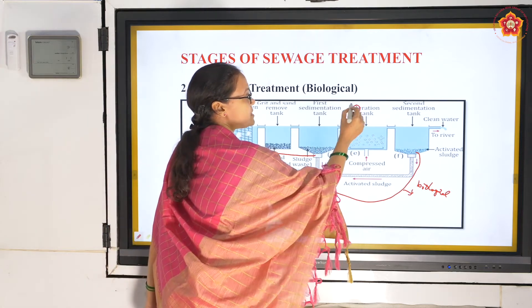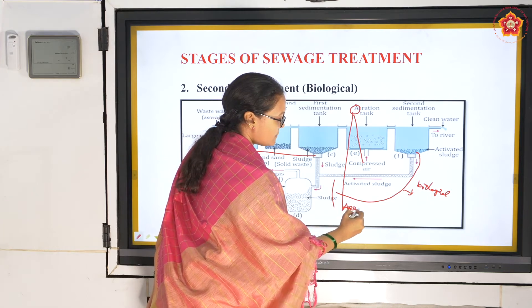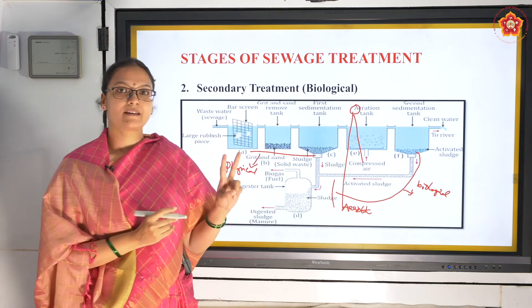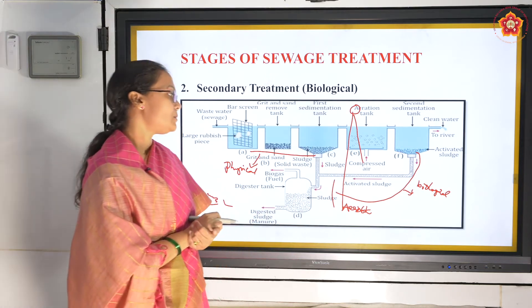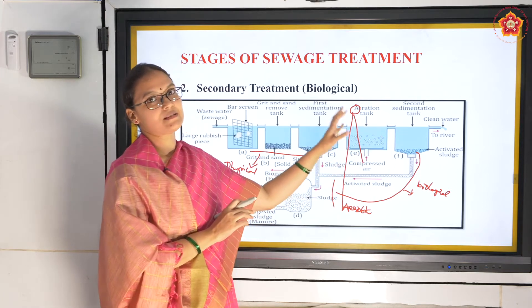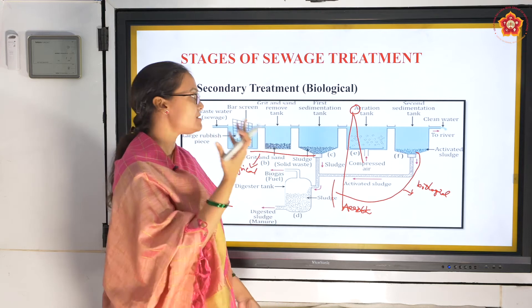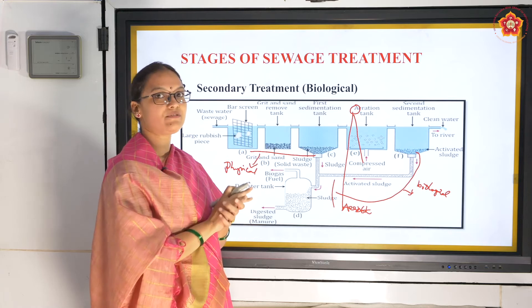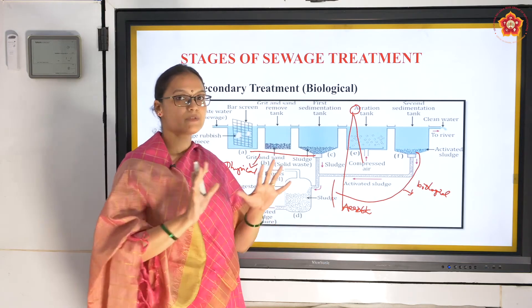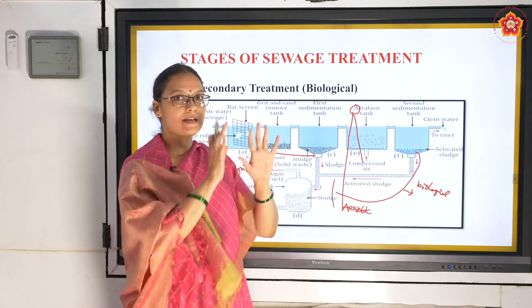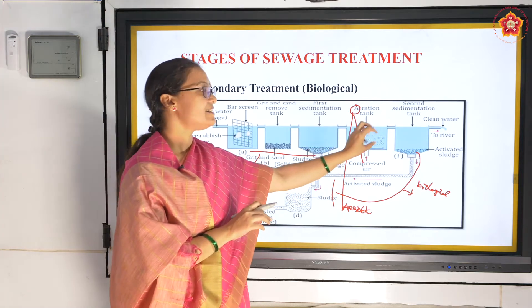In the aeration tank, two things are added: air and aerobic bacteria. The aerobic bacteria try to eat up all the organic matter present in the effluent. First aerobic bacteria are added, then air, and the tank is constantly agitated. As the aeration tank is agitated it forms something called flocs - colonies of aerobic bacteria with a mesh-like structure. The whole aeration tank is filled with these mesh-like aerobic bacterial colonies called flocs, and they start eating up the organic matter.